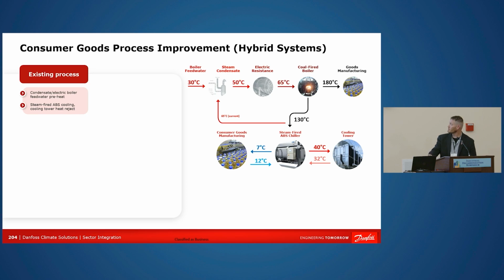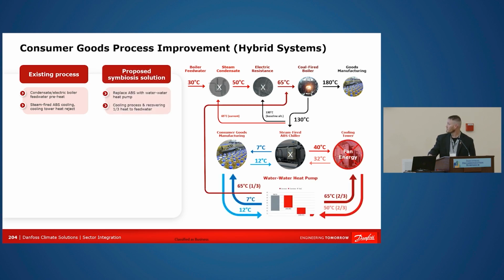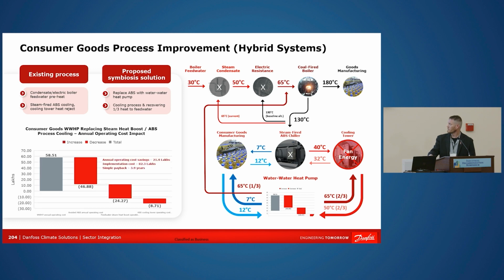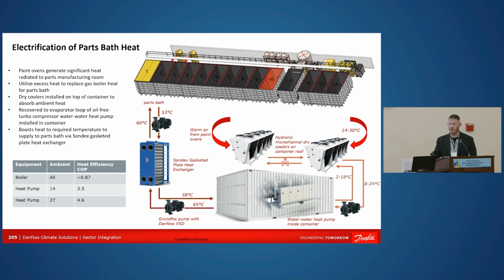Consumer goods process improvement. This is with the water heat pump replacing the steam heat boost. Electrification in a parts bath that we've utilized here and in South America as well. So we utilize our own Sondex gasketed plate heat exchangers, Grundfos pumps, because I love Grundfos, hydronic microchannel coolers, back to the parts bath, and a water heat pump. And then with the equipment, the boilers, the heat pumps, also with the regular heat pump, you get the COP of 4.6 at the end.